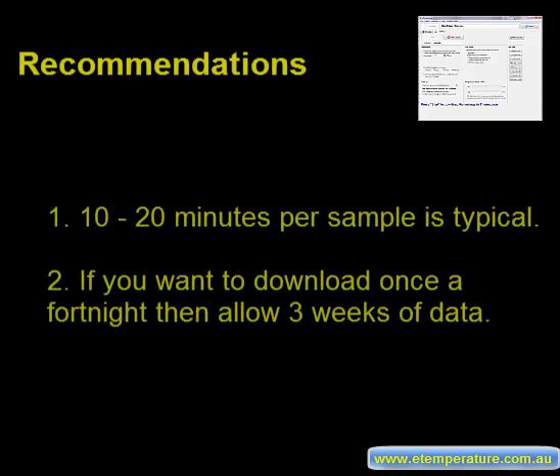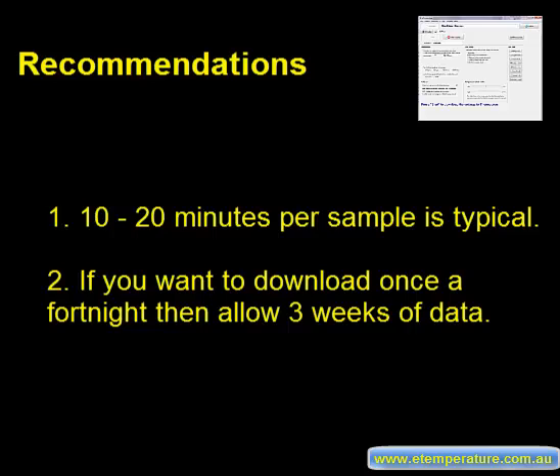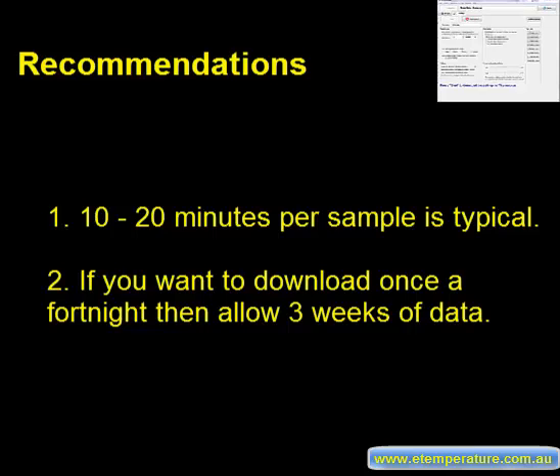For people who don't know what sample rate to use, here are some recommendations. For most people a sample rate of 10 to 20 minutes is fine. Temperature does not change that quickly and this gives it sufficient time to track those changes. The temperature logger also takes time to respond to changes, especially if it is in contact with air. A sample rate of 10 minutes means you don't have to download the results more often than once a fortnight for the TC.